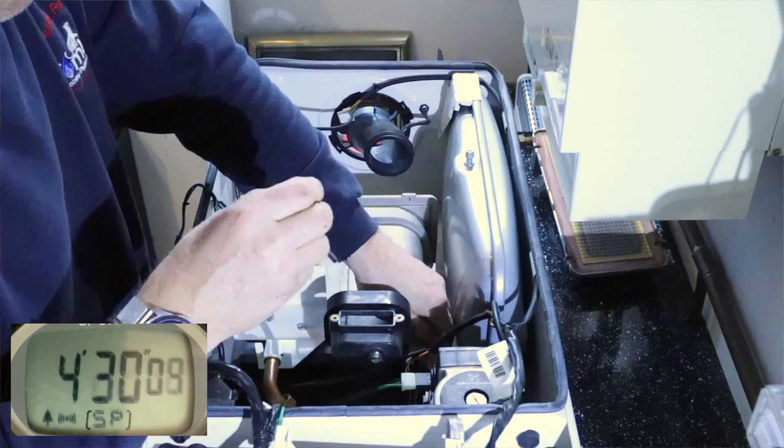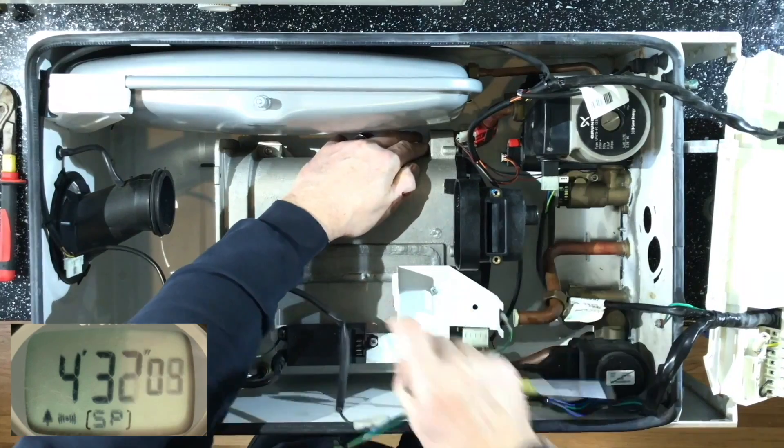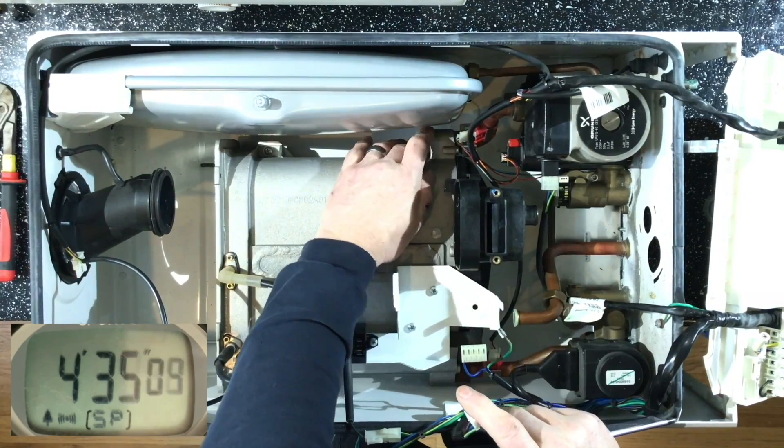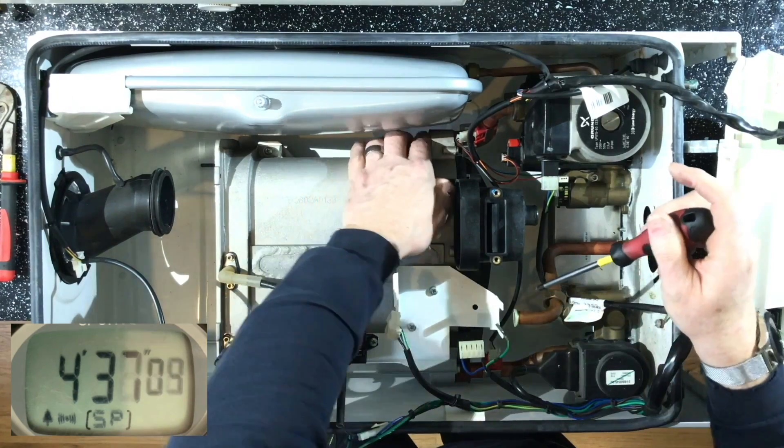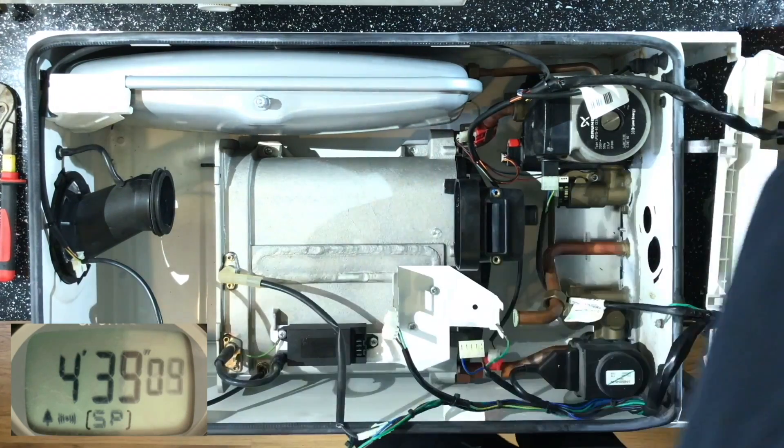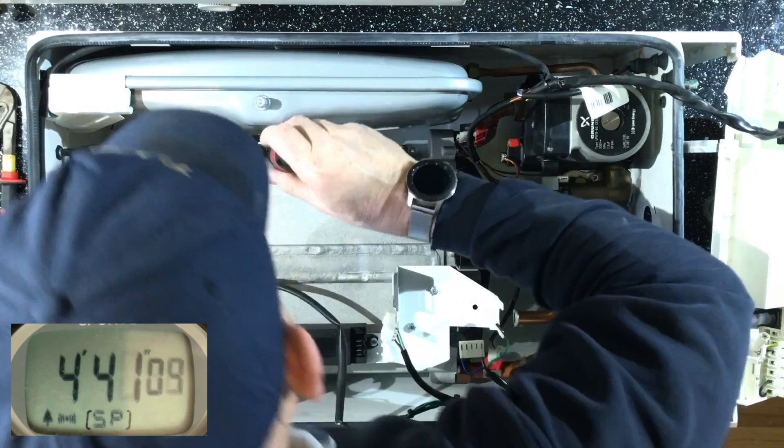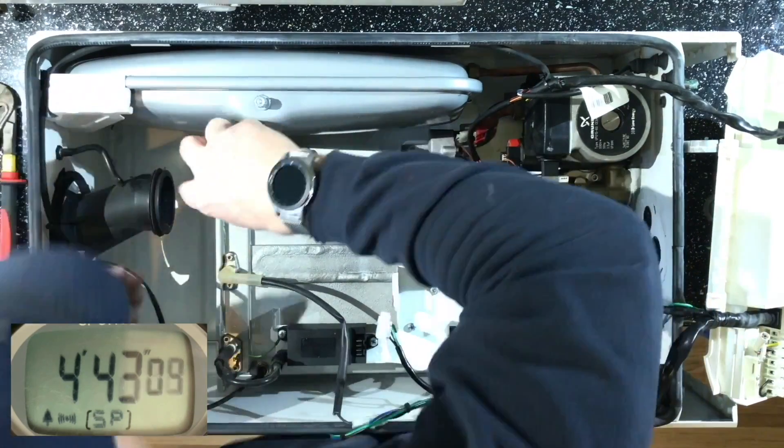So you can now see I'm removing these two retaining screws, which hold the main heat exchanger to the body of the actual boiler. So there are two screws which hold it on this side, and there are two hooks on the back of the heat exchanger which clip into the body of the boiler.